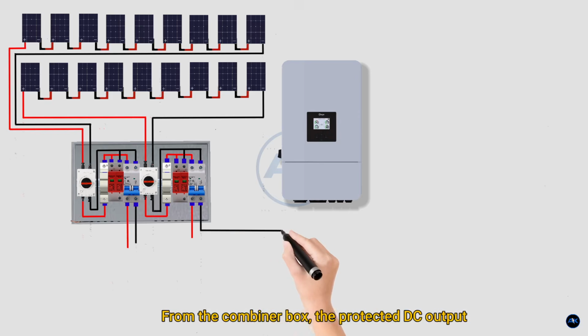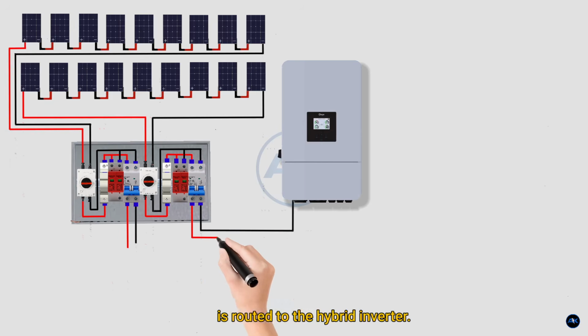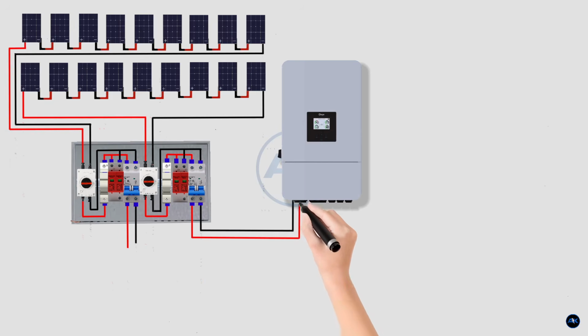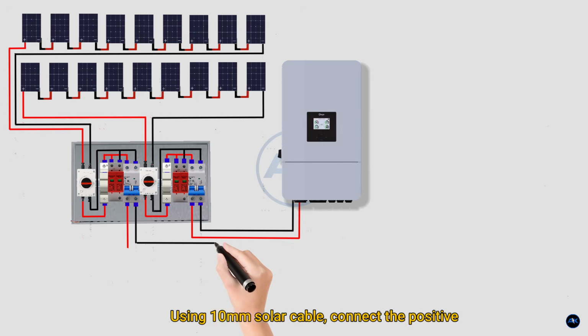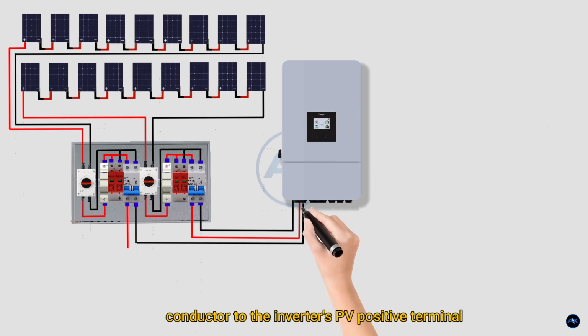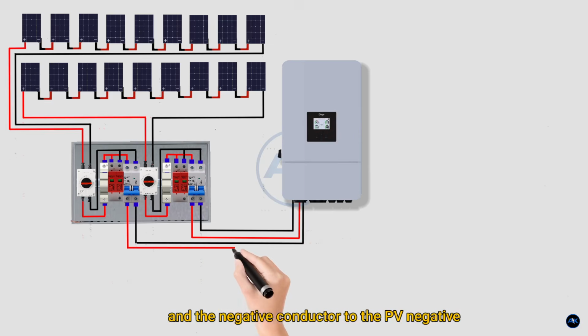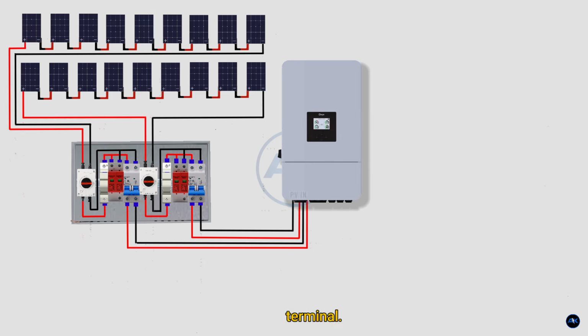From the combiner box, the protected DC output is routed to the hybrid inverter. Using 10mm solar cable, connect the positive conductor to the inverter's PV positive terminal and the negative conductor to the PV negative terminal. Double-check polarity and tighten all terminals to the recommended torque values.